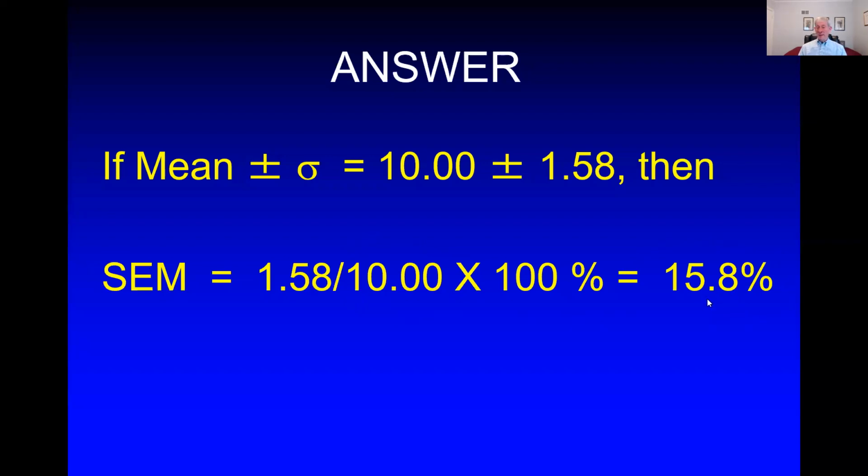And that's why you didn't like that dose calibrator. You eyeball the numbers and you could say, I don't like it. Some were 10 and 20% off, but this is the real value here. The percent error is almost 16%. What's the legal limit? 10%. And if you're really close to 10%, you probably have a dose calibrator problem. You could continue to use it because it's legal, but this, you could never use something like this.